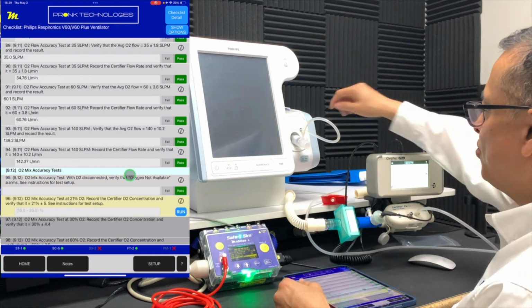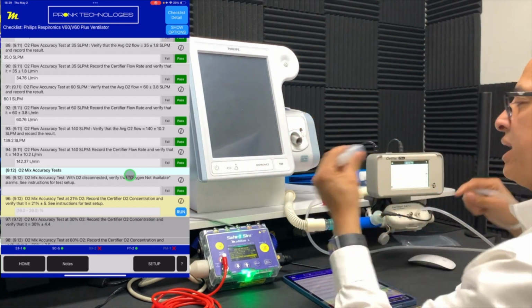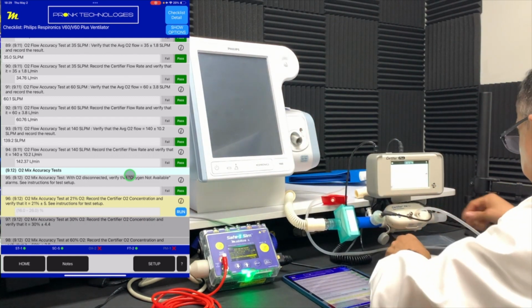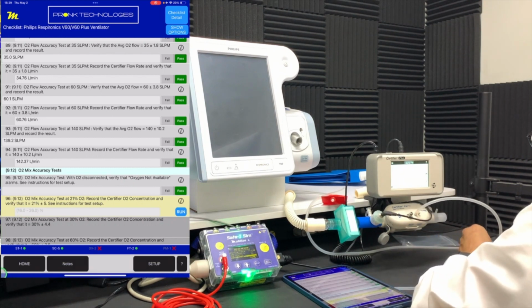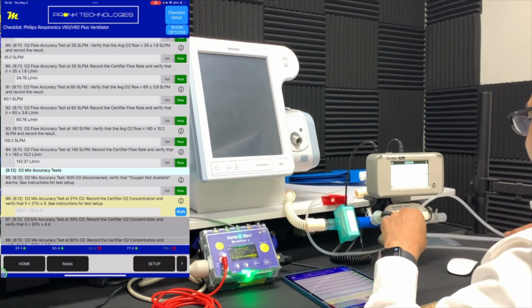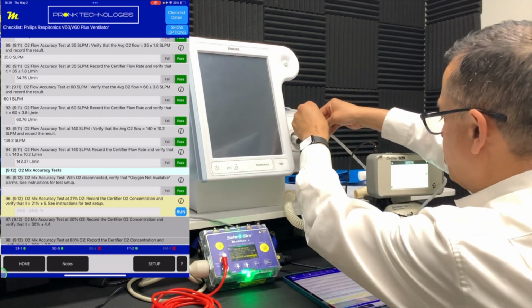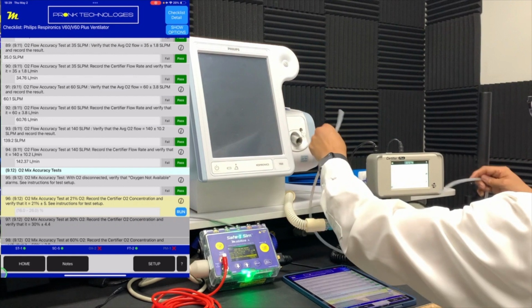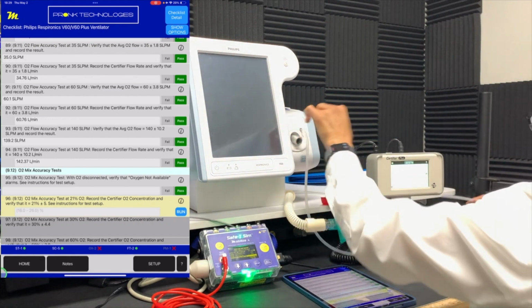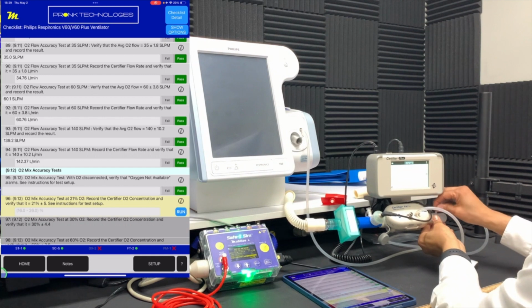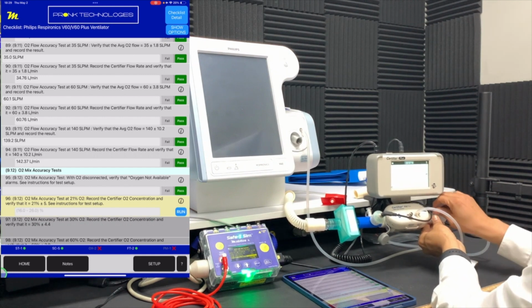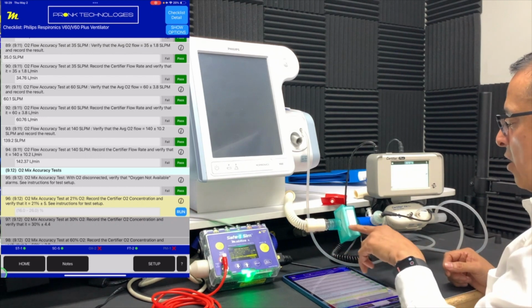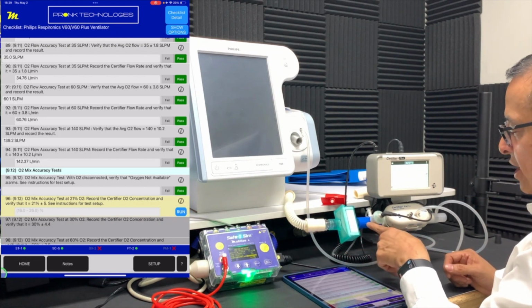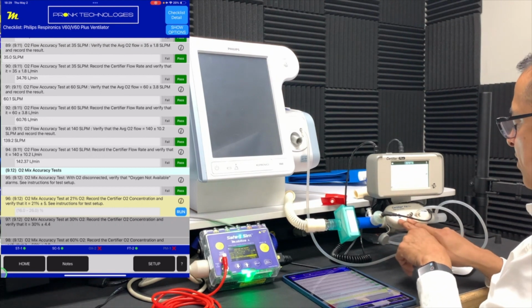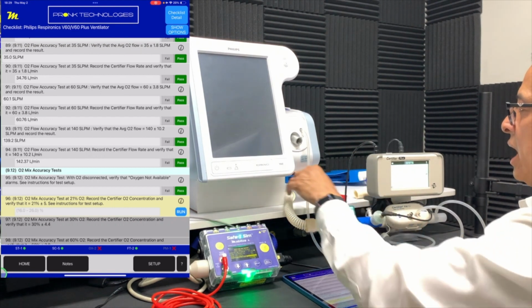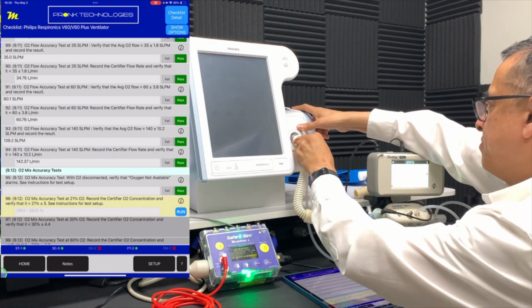And to do that, we need to configure this differently, of course. We can take this pick-off valve, connect it to the output, connect this over to here, connect our ventilator to the proximal pressure port like we had before. So let me do, we had it here. And then of course the other end, we connect the pressure port to our pick-off valve here at the output as well. And you probably noticed that now in line here, we have our oxygen sensor connected to the circuit. So this is what we're going to utilize with the FA Certifier Plus flow module here to measure the oxygen concentration. So let's go ahead and connect this up to it here.